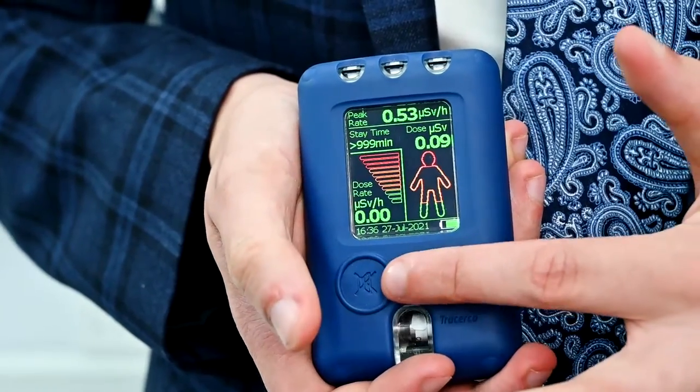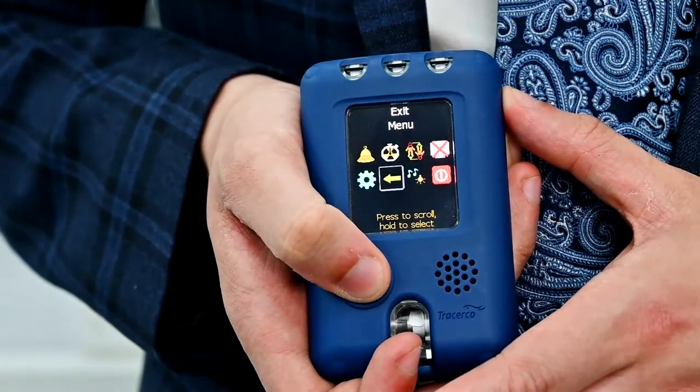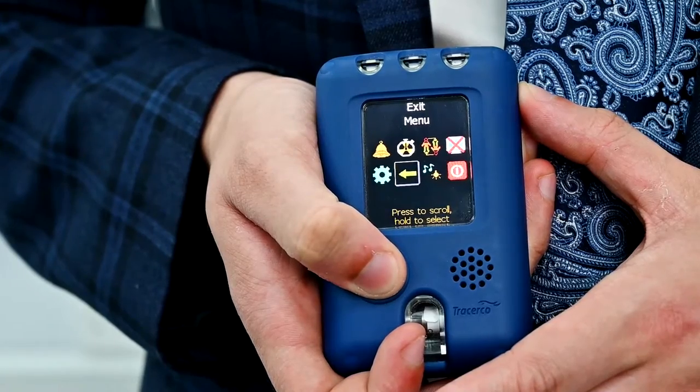The PED's menu is navigated using a one-button system, making it ideal for even untrained members of staff. In the menu you can view the alarm levels you've set, enable screensavers, and enable settings such as the activity sounder, which will make your PED produce clicks synonymous with radiation when you're taking your readings.